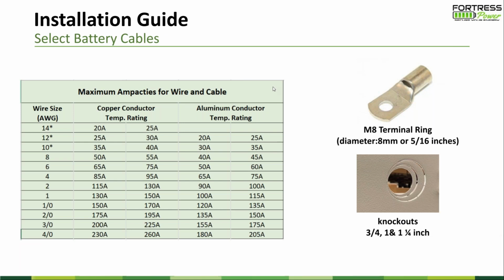So it's pre-made already. And on the left side, I give a little bit of amperes reading on the battery. So you want to choose the correct wires based on the battery you picked. I propose you always look at the circuit breaker. You want to size a little bit bigger than the circuit breaker, so that will protect the conductor. Just let the circuit breaker break first, before the wires start melting.